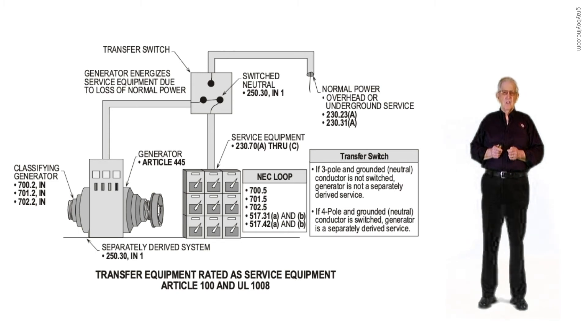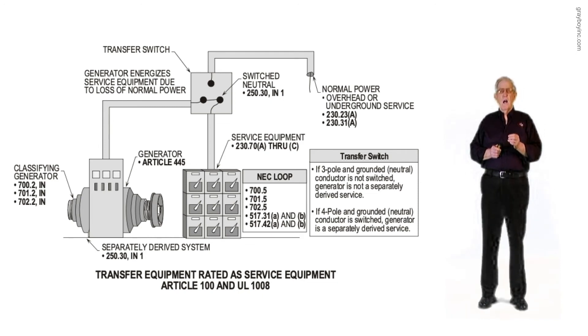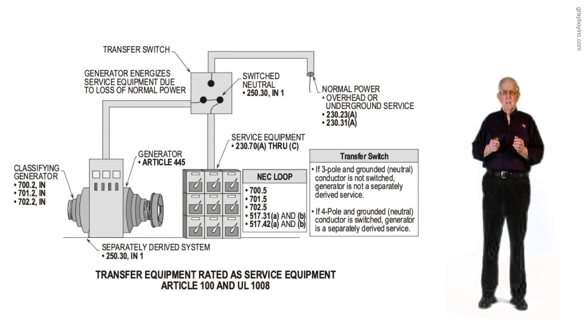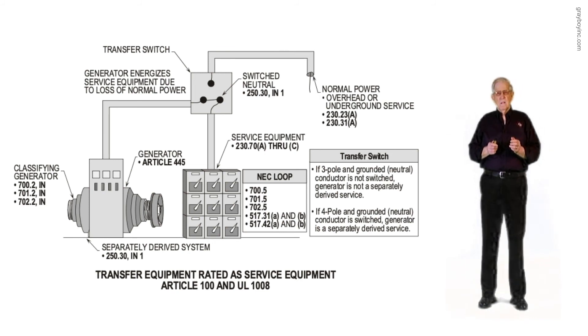The NEC loop suggested for review for that transfer switch includes: 700.5 if it's an emergency transfer switch — is it service equipment, is it permitted to be service equipment, or is it not? 701.5 for legally required standby, and 702.5 for optional standby type generator. And if you happen to be in healthcare facilities, 517.31A and B and 517.42A and B, which is reviewed in volume two of Stallcup's Electrical Design book.